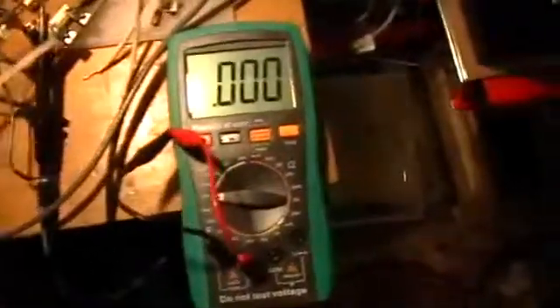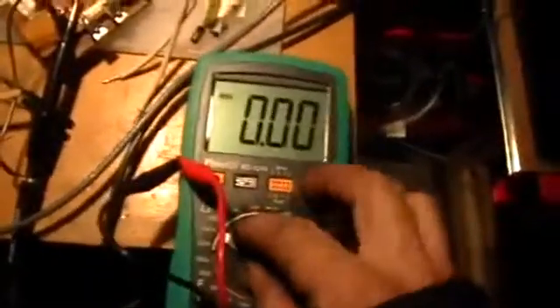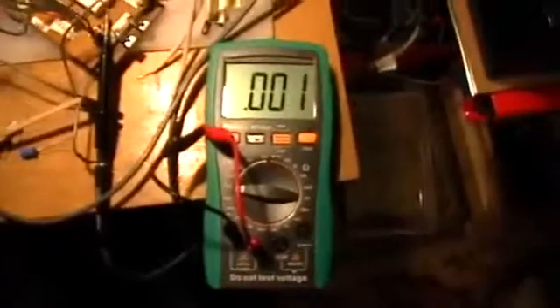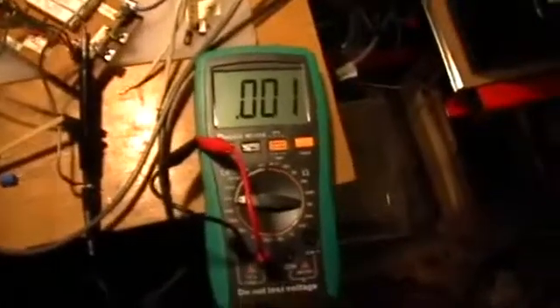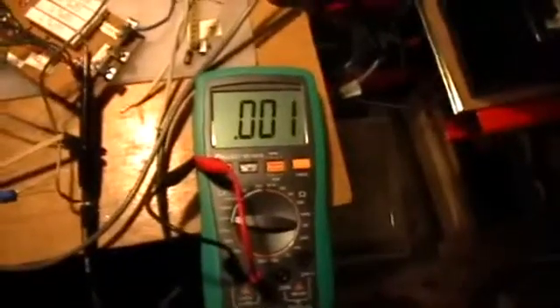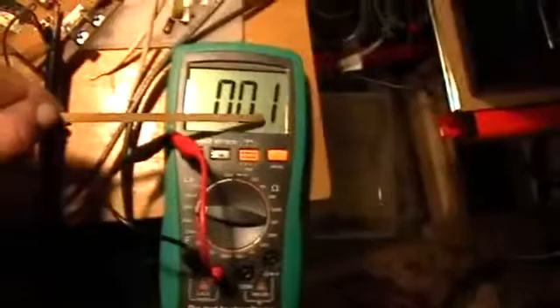So let me do this little trick here. I'll switch the range up, and then back down, and let it go through its thing again. So one, and then maybe after a little while it might drop down to zero, which is telling us that it's somewhere close to one microhenry of inductance in the leads alone.